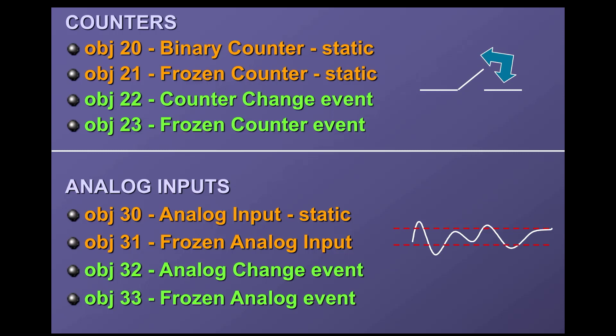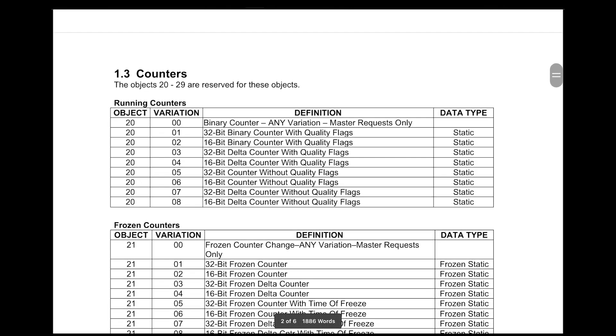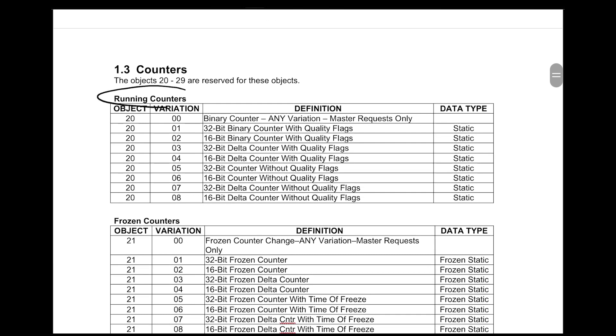When it comes to counters, you can have running counters, frozen counters, and counter events. Object 20 is a running counter — that's the traditional counter you've looked at with Modbus. Every time there's a new count, it updates the count. It's a static data type — the real-time value in that counter. When it comes to object 21, this is something called a frozen counter.